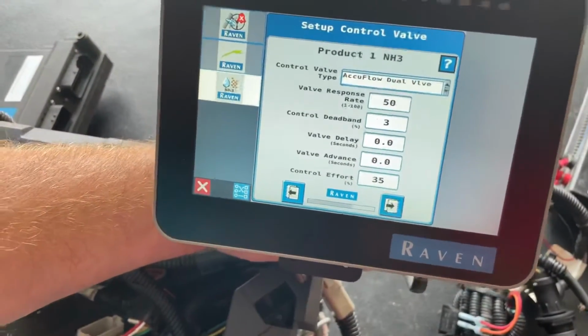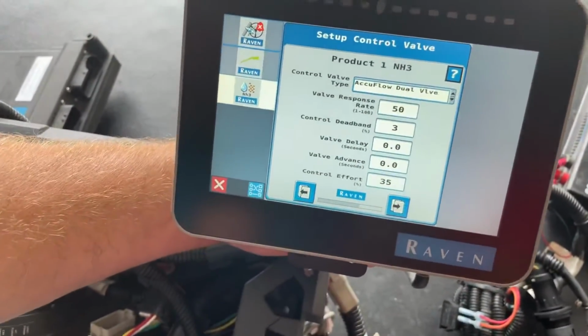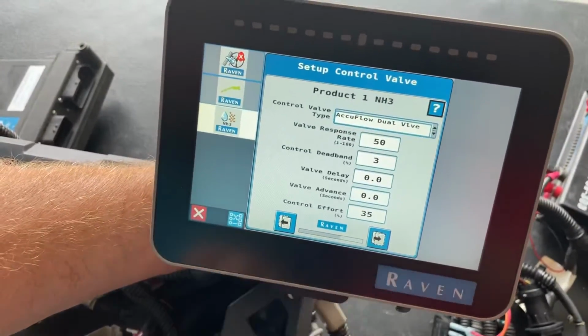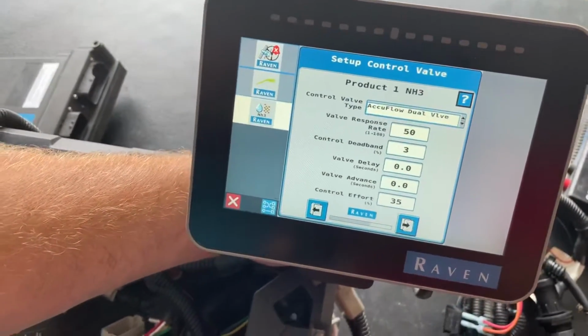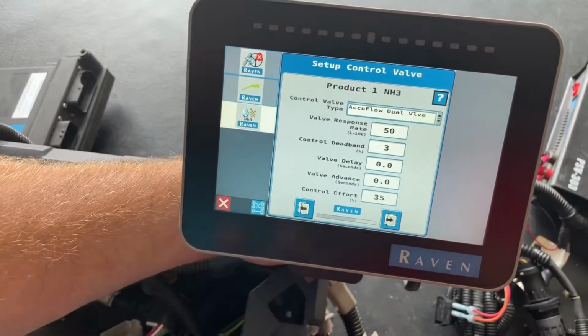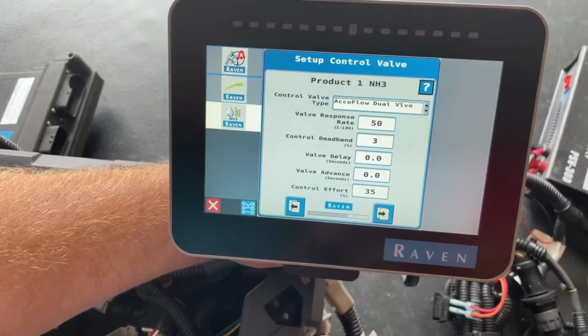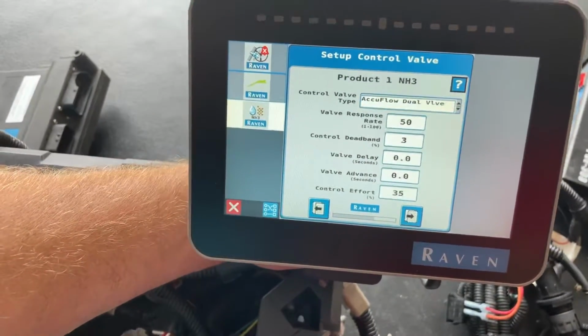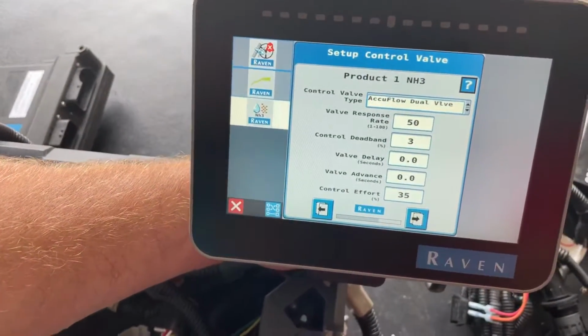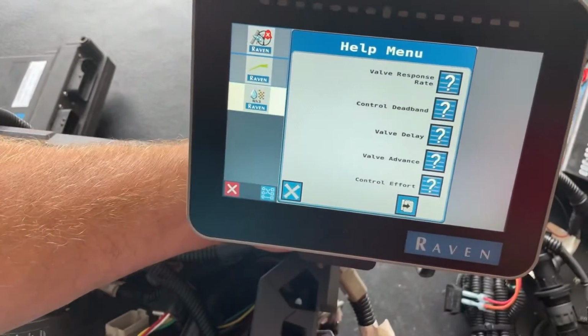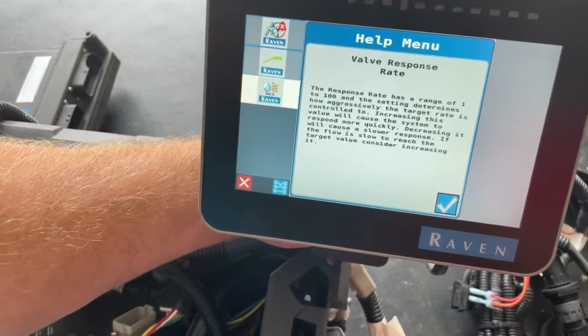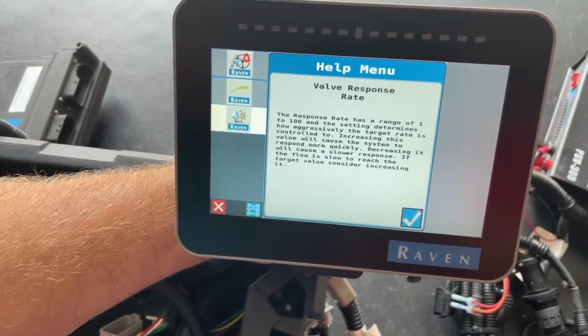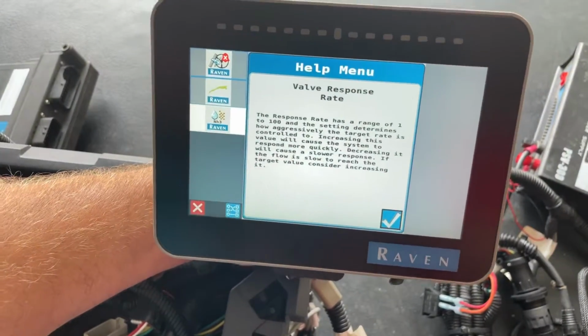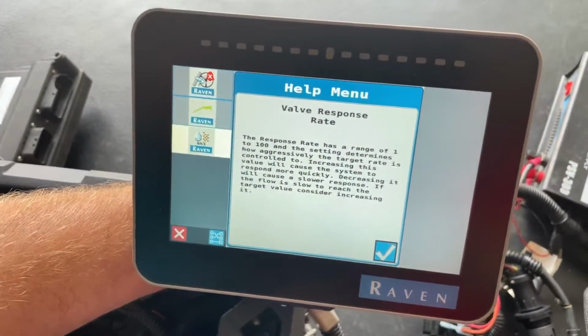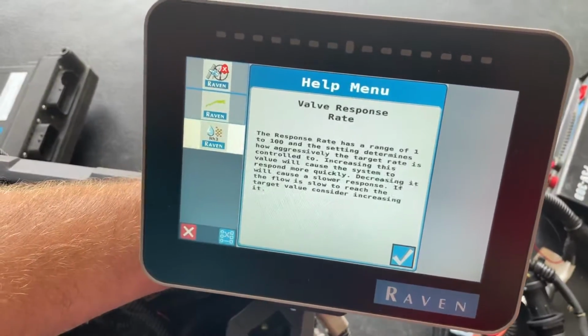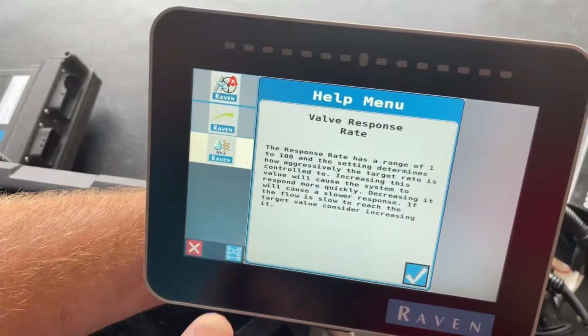Now we've got, instead of valve count numbers, we have response speed, control deadband, and valve control effort. Our deadband we're not going to mess with. That's always been at 3%. These are already factory set for a good starting point. Response speed is how fast the valve reacts. But Kent, say you forget about something, you can always hit the question mark and go to valve response speed, and now it'll give you kind of a quick definition. So throughout the system, anytime you see anything with it and you're not for sure, that question mark up in the corner can always help get you the answers.